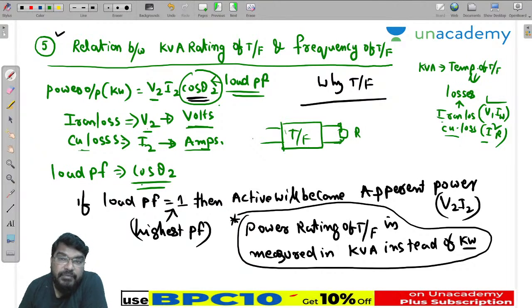So that's why the manufacturer considers the highest power factor of the load, so that you can operate at any power factor. If it is 0.1, we cannot operate at more than 0.1. So that's why we design with the load power factor equal to 1. If the load power factor is equal to 1, then active power becomes apparent power.